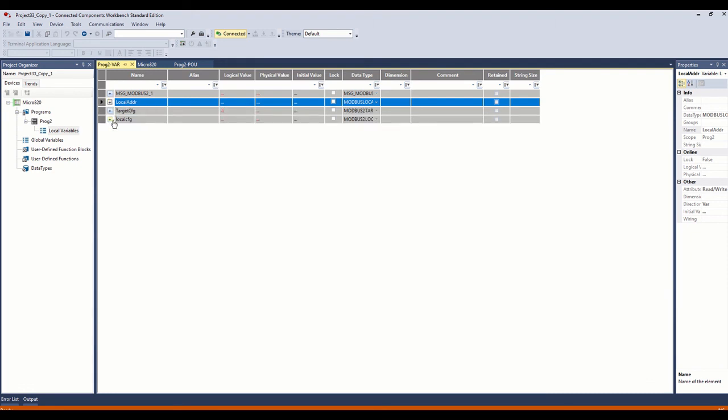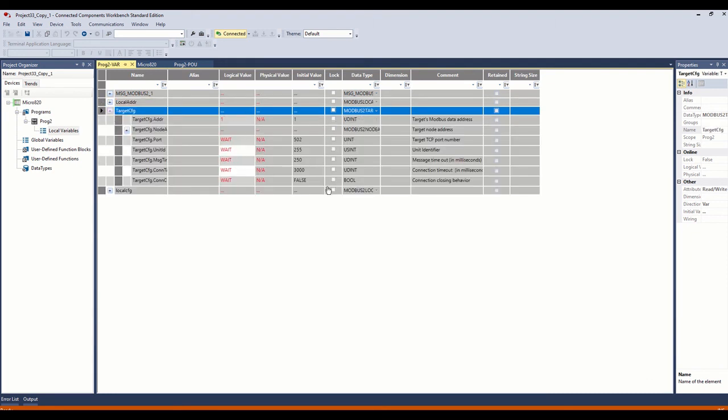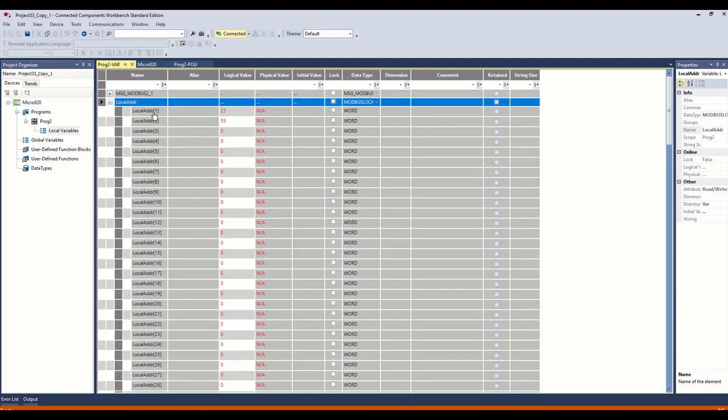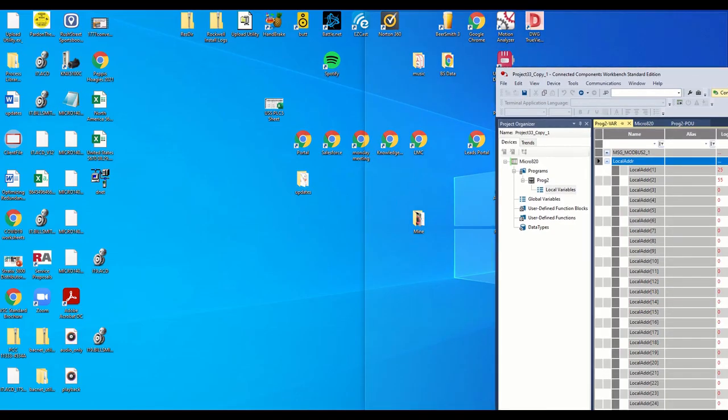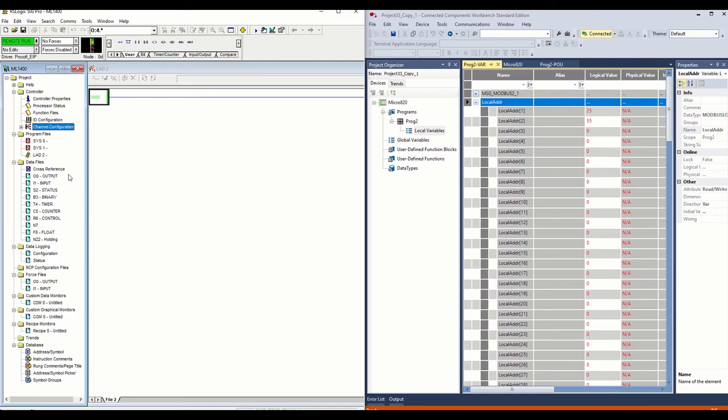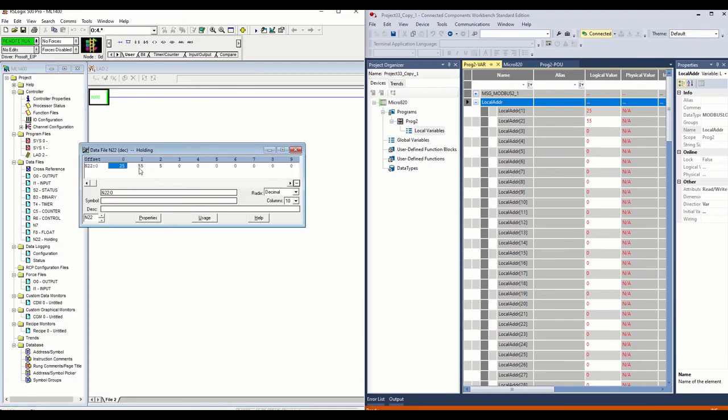You can see we have some data in here in our first two. Remember under our local config, the number of elements we're reading, we're reading two. So under our local address, we have two integer values coming in. So let's go ahead and go half screen on this and open up our holding registers here. You can see 25 and 55 equal our 25 and 55 here.